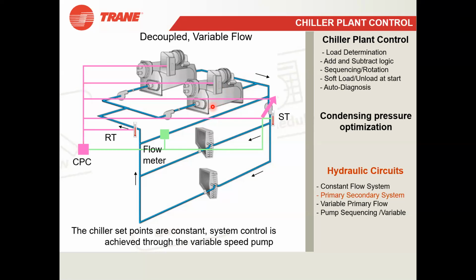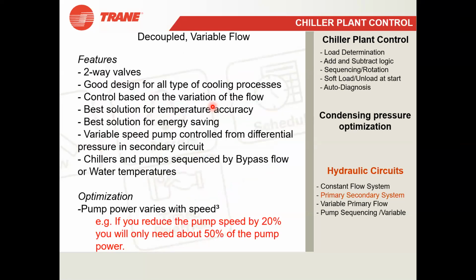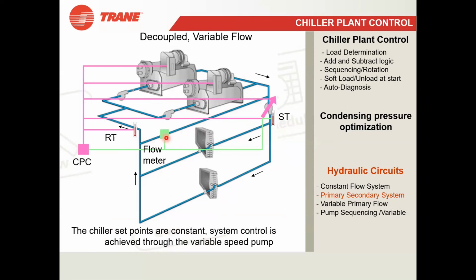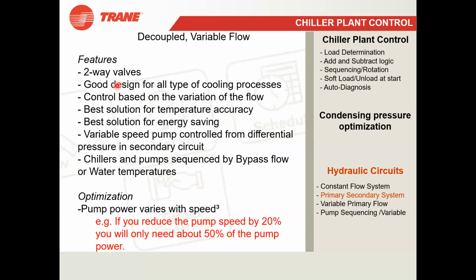And I will show you actually. Yeah, so these calculations are given here. You know what all decoupled variable flow has. I have already told you that a flow meter has to be there, because all the time flow has to be monitored. There is a return temperature sensor, there is a supply temperature sensor. There are two-way valves in both the lines. Okay, so that has been told, how you will be configuring this system.